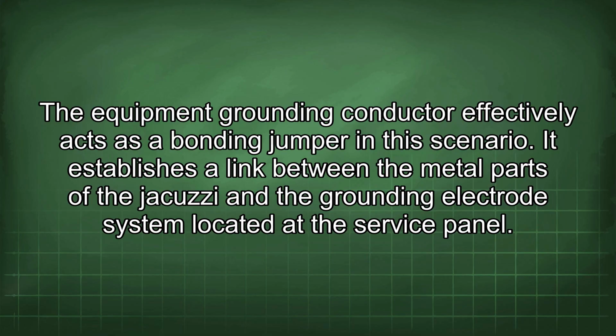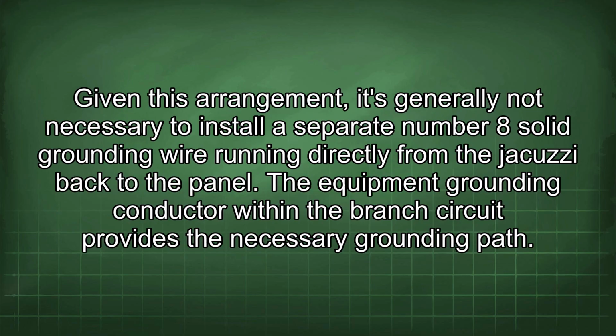It establishes a link between the metal parts of the jacuzzi and the grounding electrode system located at the service panel. Given this arrangement, it's generally not necessary to install a separate number 8 solid grounding wire running directly from the jacuzzi back to the panel. The equipment grounding conductor within the branch circuit provides the necessary grounding path.